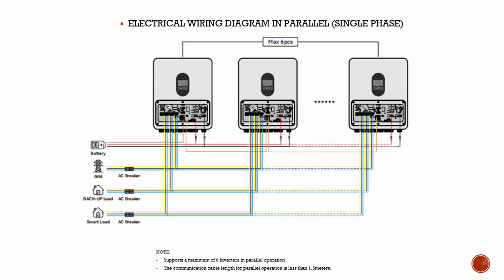So all of our inverters have 2 parallel ports, PRA and PRB. So let's say you're paralleling 3 units together. You have to connect one end of your cable to PRB on the master, to the PRA of the slave, then from the PRB of the slave to the PRA of the last slave.